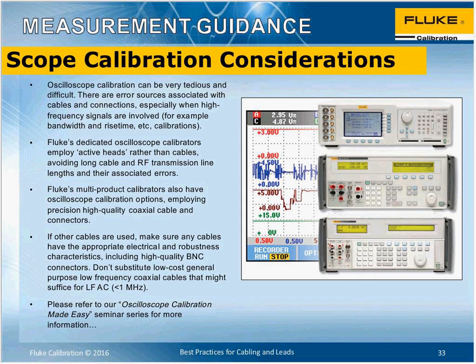at the top, or the multi-function, multi-product calibrators with oscilloscope calibration options, can take care of some of that stuff, because the 9500, for example, uses active heads to deliver the signals directly to the oscilloscope input, thus avoiding the issues with long transmission lines and long cables by making that direct connection. The multi-product calibrators that have oscilloscope calibration options typically don't go up so high in frequency with their leveled sine outputs for bandwidth calibrations or the speed of the fast edges.